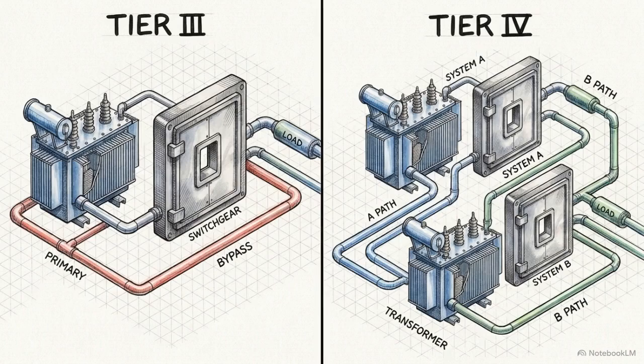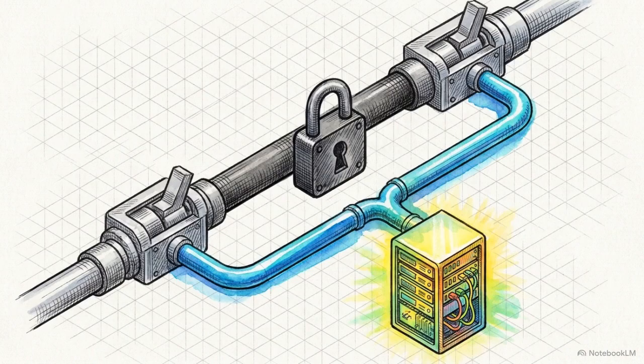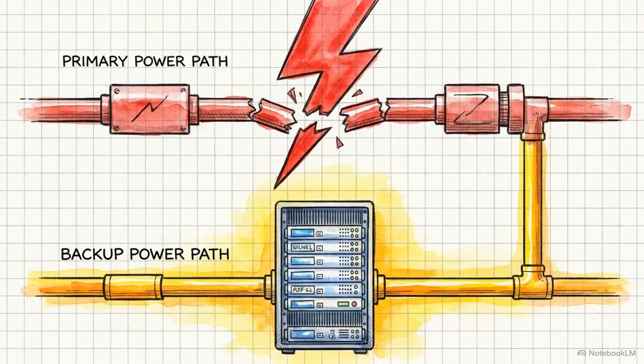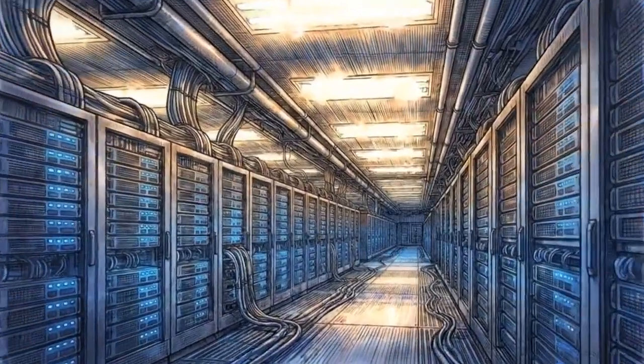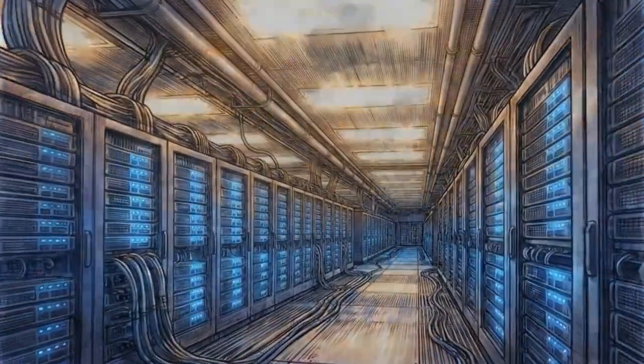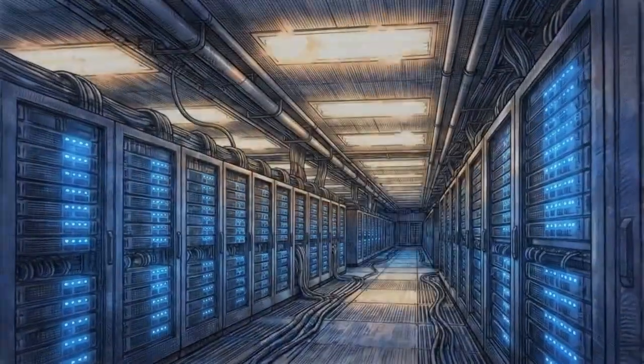Resilience evidence is categorized by the project's compliance target, specifically Tier 3 concurrent maintainability or Tier 4 fault tolerance. Tier 3 evidence requires a demonstration that any single power or cooling path can be manually isolated for maintenance without impacting the critical IT load. Tier 4 evidence requires the facility to automatically survive an unplanned failure across active power or cooling paths without any loss of capacity. Ultimately, documented and measured behavior under extreme operational stress provides the only reliable proof of true data center resilience.